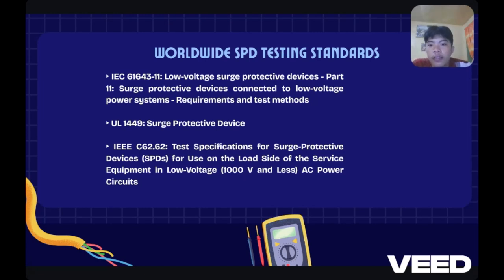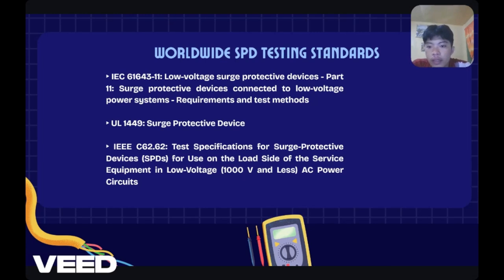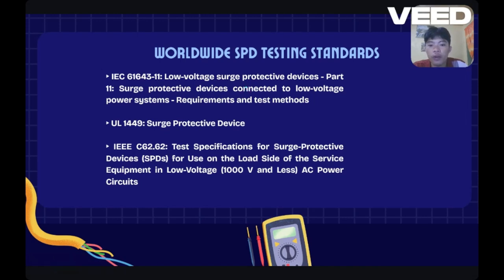Worldwide SPD testing standards: we have IEC 61643-11, low voltage surge protective devices, part 11. So we have surge protective devices connected to low voltage power systems, requirements and test methods. We have UL 1449, surge protective devices, then IEEE C62.62, test specification for surge protective devices for use on the load side of the service equipment in low voltage, 1000 volts and less, AC power circuits.